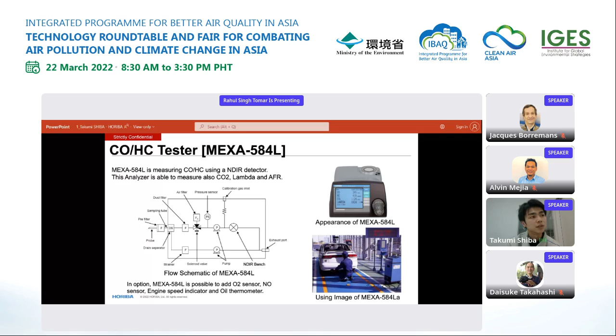This figure shows the gas flow inside the Mexa 584L device. Mexa 584L is equipped with a pump which sucks exhaust gas. Exhaust gas is sucked from the tip of the probe, passes through the filter attached to the probe, and enters the device. Inside the device, the drain separator first separates the gas and water. The gas component passes through the dust filter and pump, and the CO and HC concentrations are measured on the NDIR bench, and the gas component is discharged from the exhaust port. In addition, the Mexa 584L can optionally connect an O2 sensor and NO sensor and engine speedometer and oil thermometer. Okay, please move to the next slide.